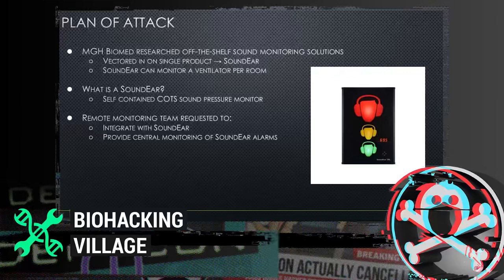So you can hook a SoundEar with a microphone up to the speaker on the ventilator that auditorily alerts the alarm. And then when the sound pressure is exceeded, when that alarm goes off, the SoundEar can then trip. So we were then requested to integrate with this SoundEar and provide a central means for monitoring the SoundEar and be able to create a central dashboard for when it trips.